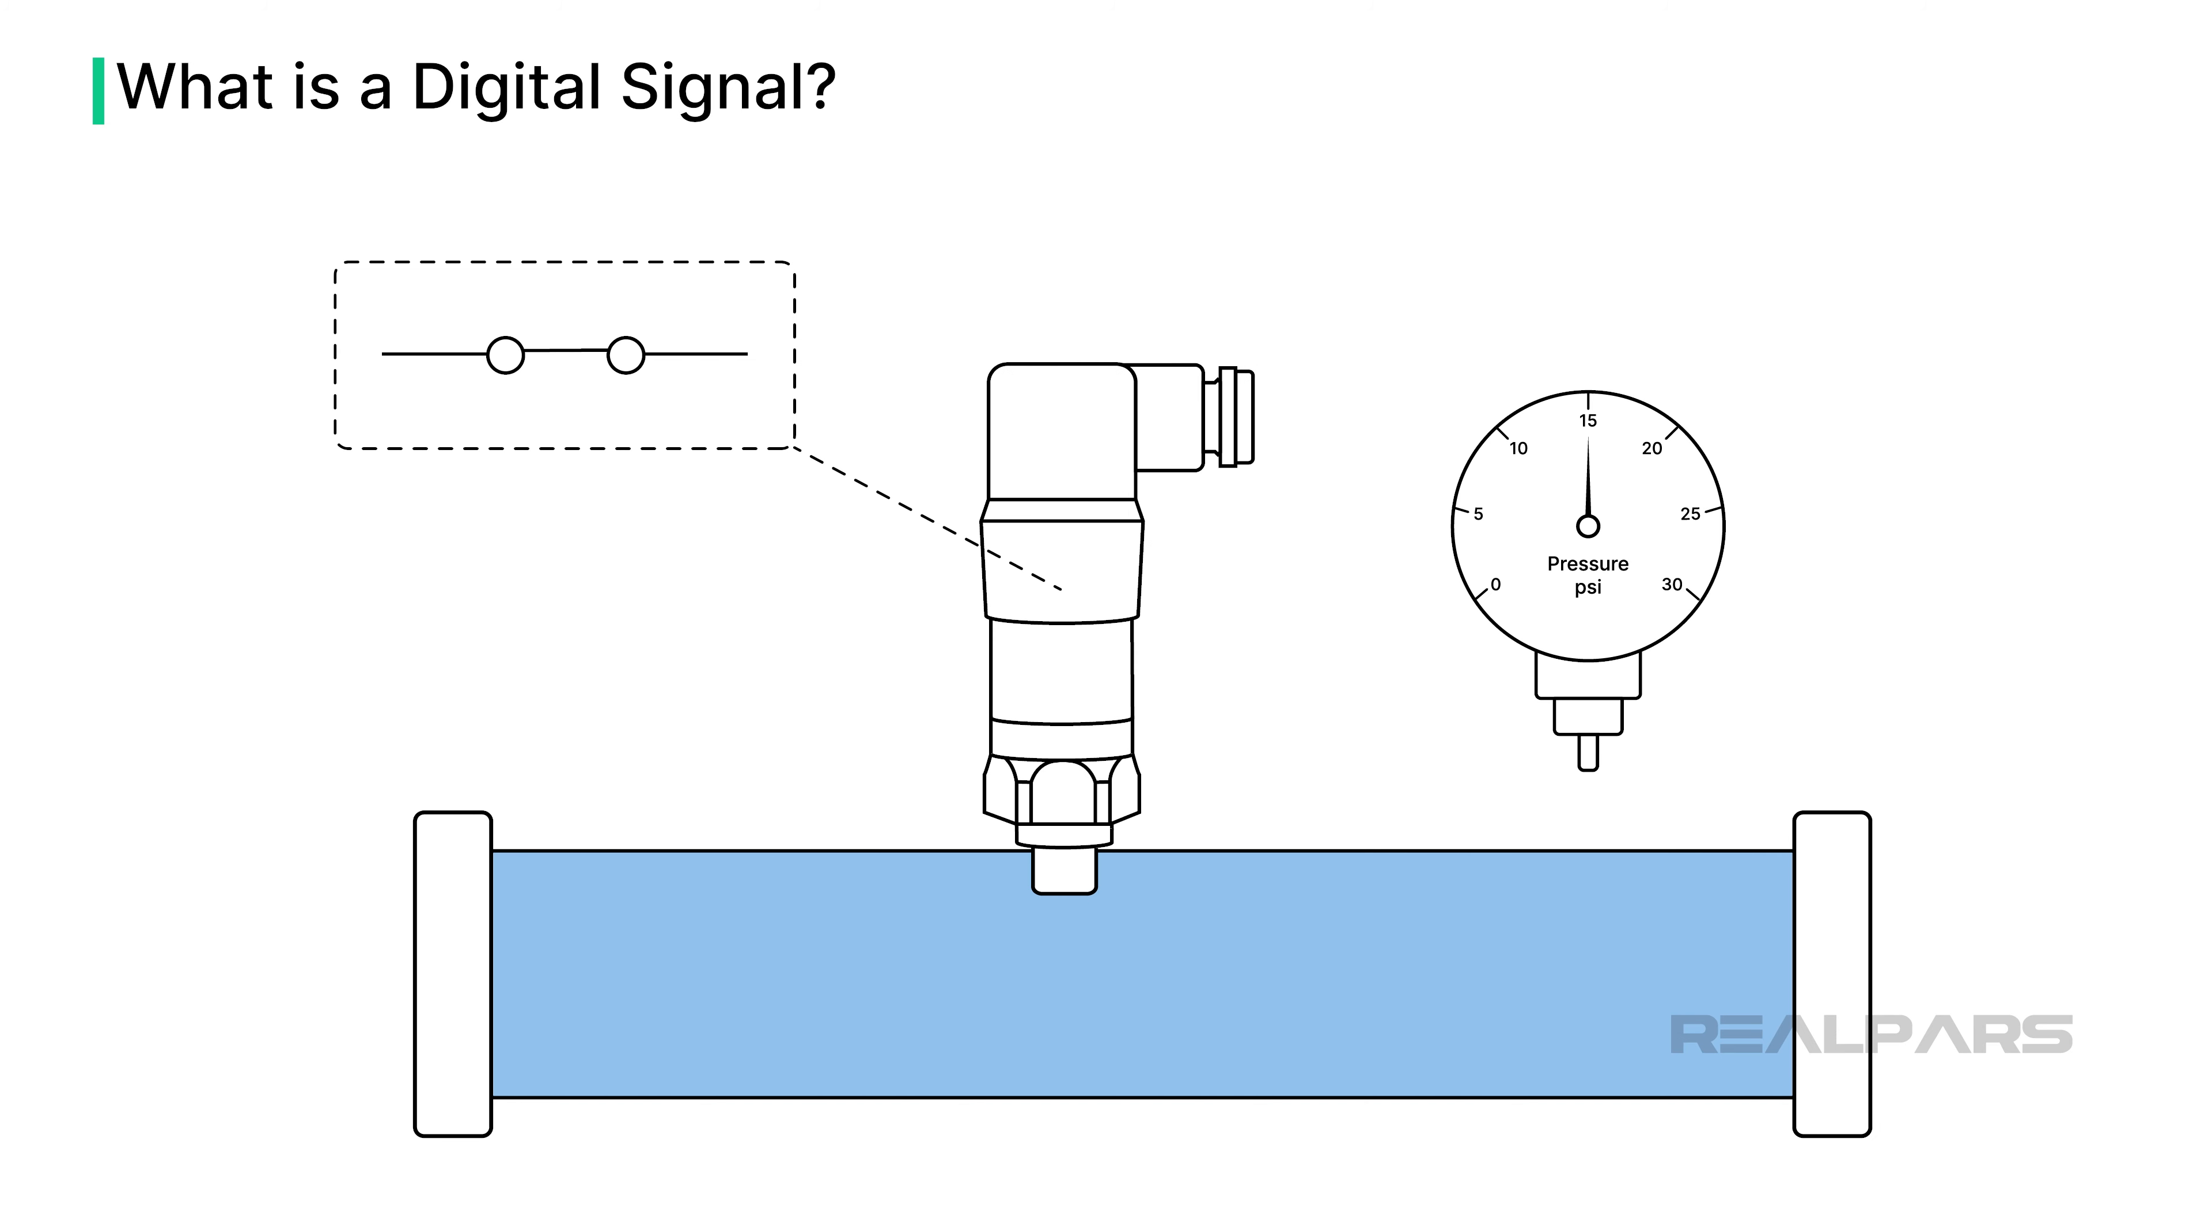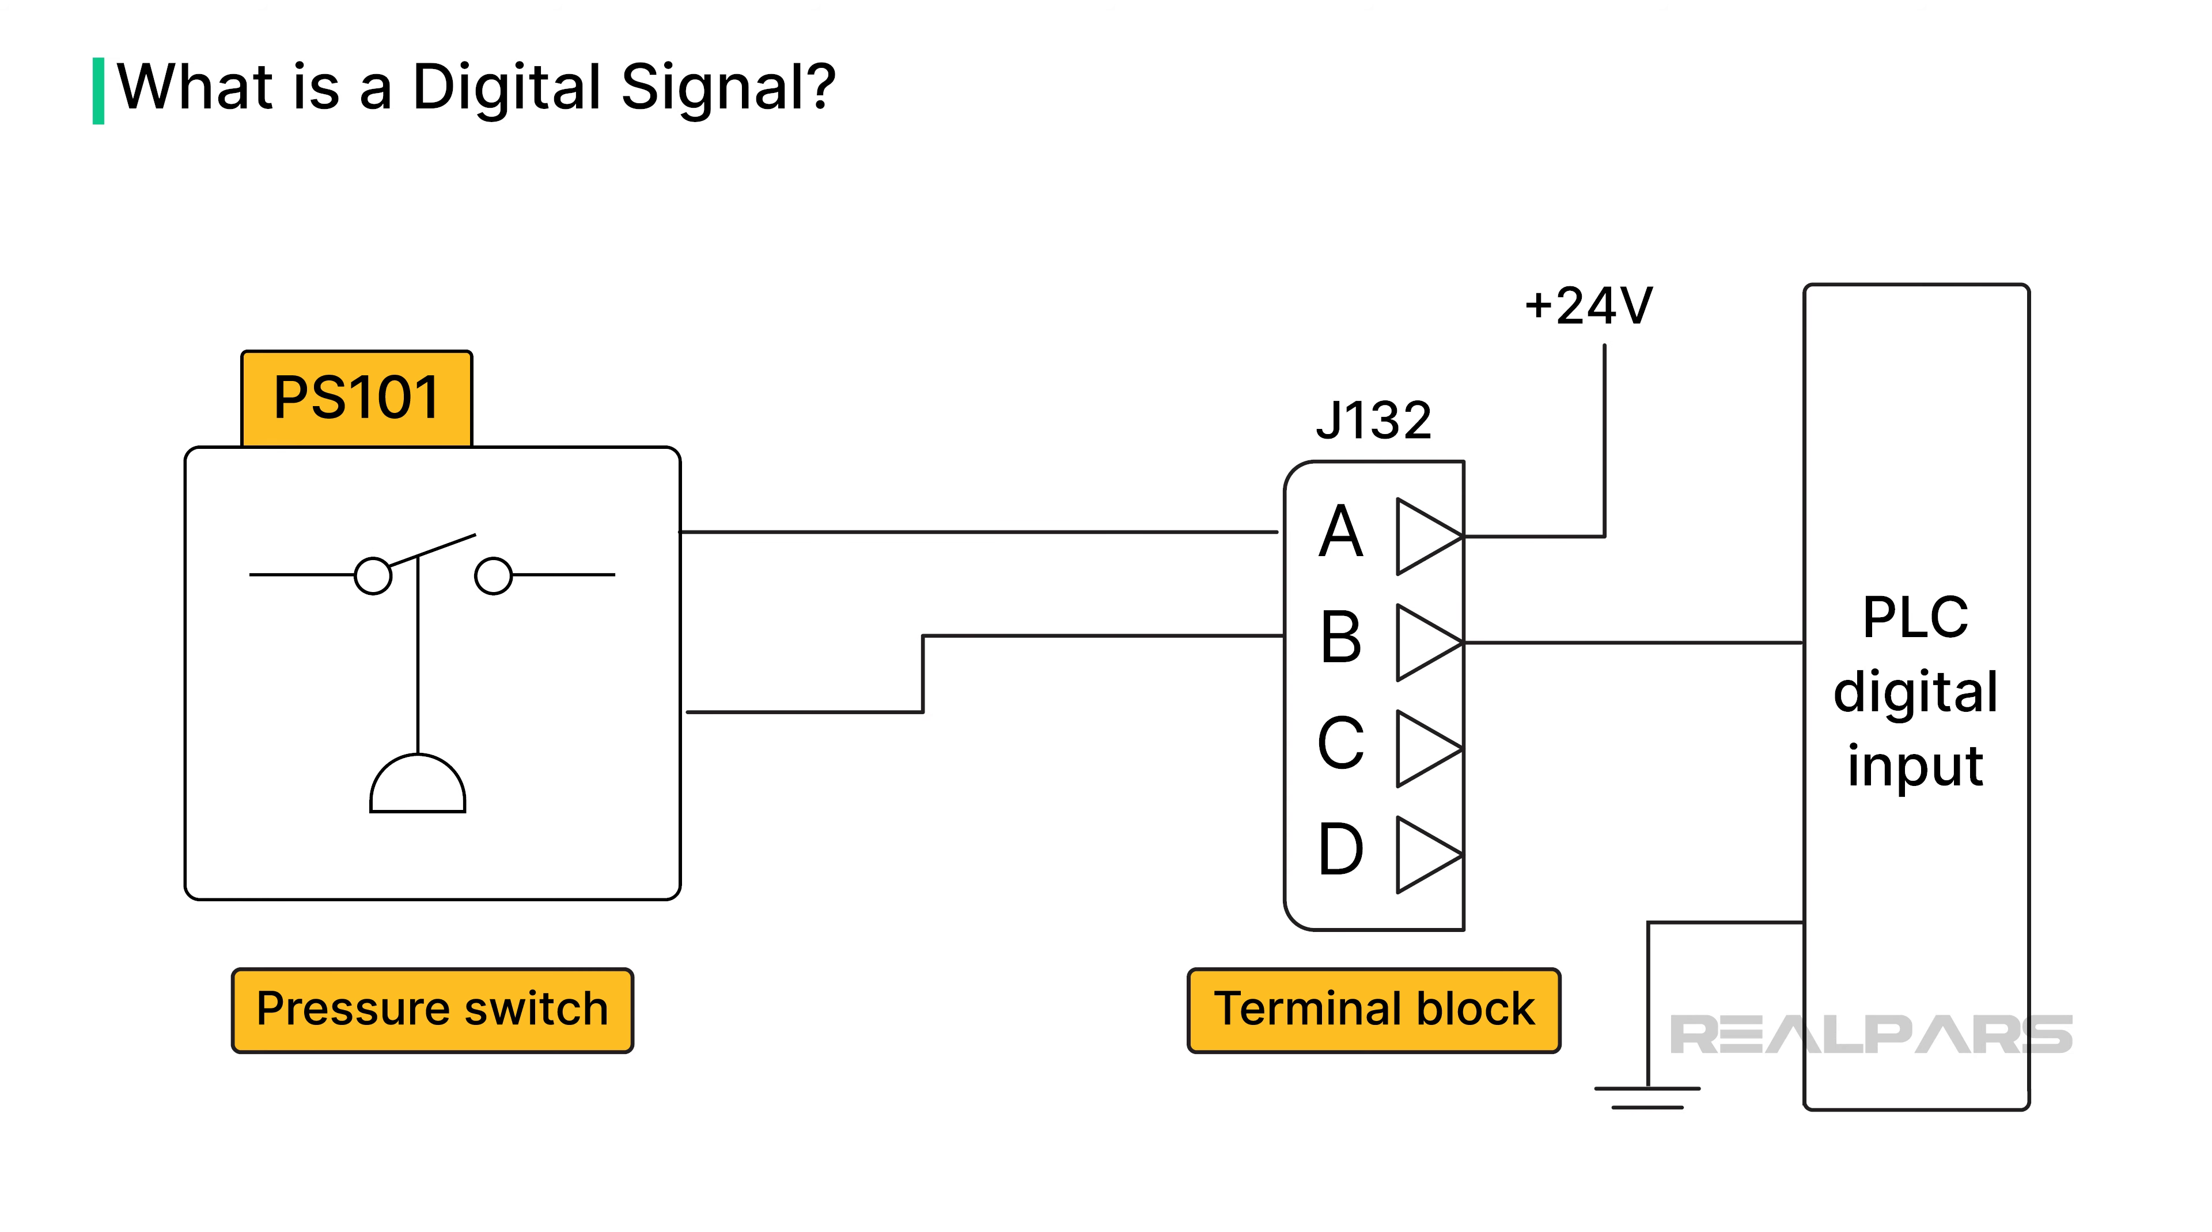Let's look at a pressure switch, a digital field device that operates at a specific pressure of 15 psi. This means the switch is open at pressures below 15 psi and closed at pressures above 15 psi. We can connect this switch to a digital PLC input with a bit of simple wiring.